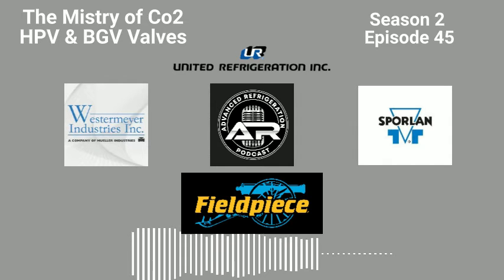So you have a couple different options here. Danfoss has a stepper motor on theirs. They have one with a CCMT, which is a stepper motor driven valve. So it would be a bipolar stepper motor. It's getting a bipolar signal, an open and closed signal from a 326A, an iPro controller, whatever is driving that. You could be using the E2 to drive that. I've used the E2 to drive a high pressure valve, a multiflex board.